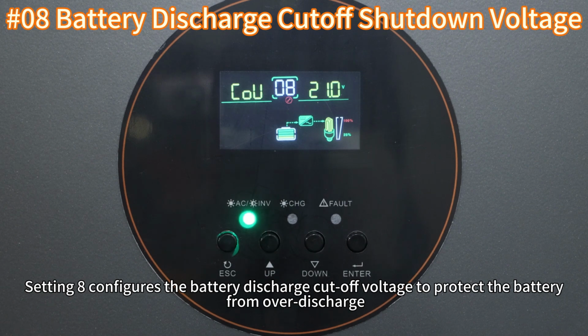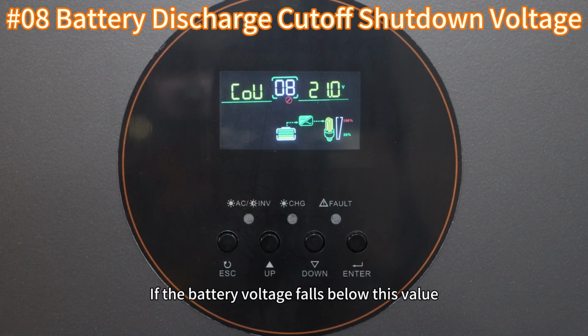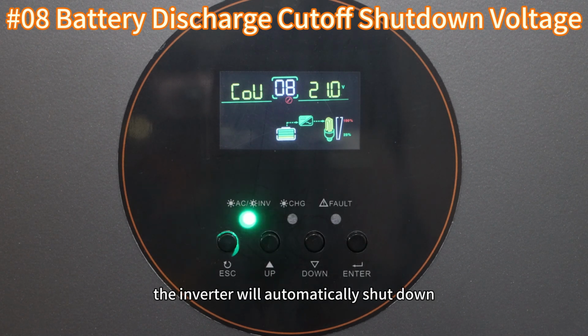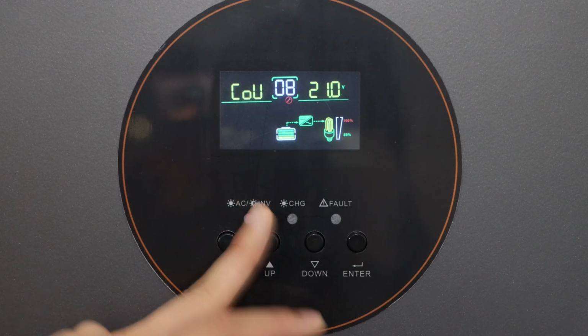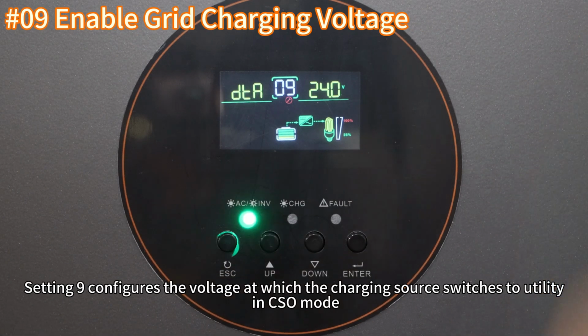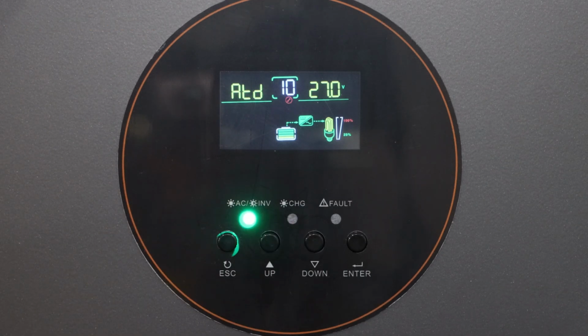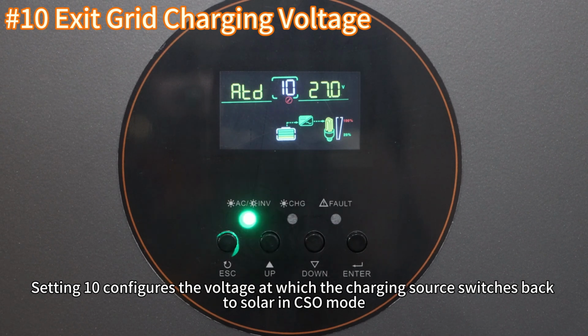Setting 8 configures the battery discharge cutoff voltage to protect the battery from over-discharge. If the battery voltage falls below this value, the inverter will automatically shut down. Setting 9 configures the voltage at which the charging source switches to utility in CSO mode. Setting 10 configures the voltage at which the charging source switches back to solar in CSO mode.